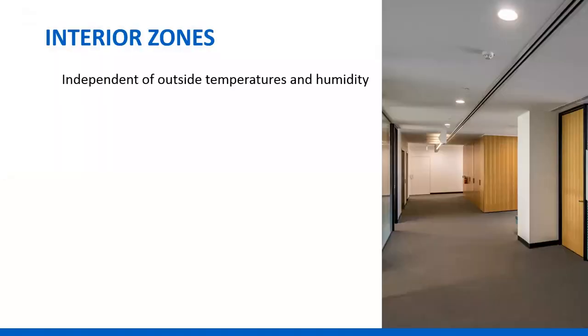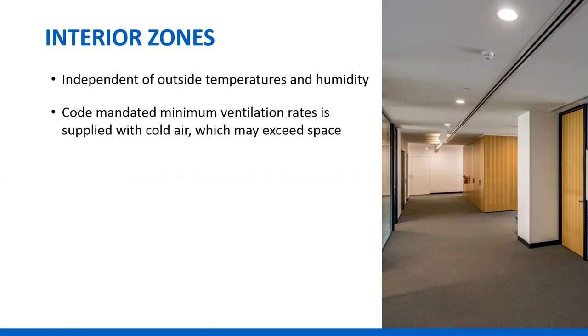Interior zones, typically more than 15 feet in, are independent of outside temperatures and humidities pretty much. The ventilation air is not, but the space itself is pretty much isolated from what's going on outside. We have mandated minimum ventilation rates, and humidity control is required in the interior zone as well.